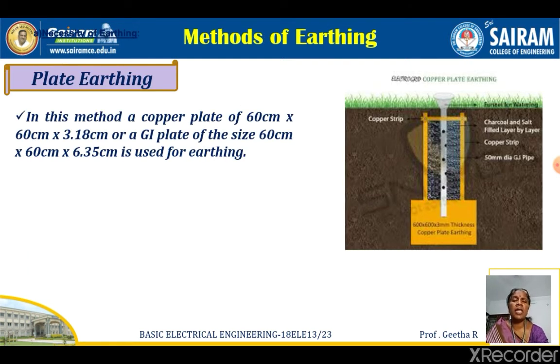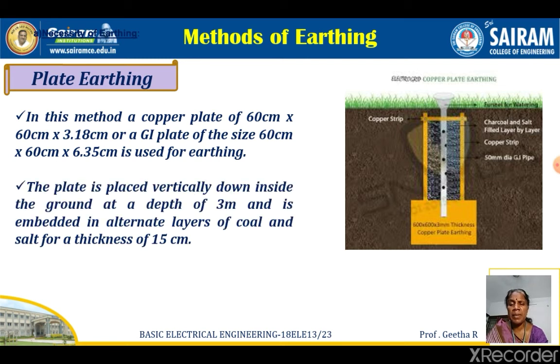Methods of earthing. There are two types of earthing called plate earthing and pipe earthing. Plate earthing is nothing but a copper plate that is kept inside the ground. In pipe earthing, a pipe is used for the earthing. In plate earthing, a copper plate of 60 centimeter by 60 centimeter by 3.18 centimeter, or a galvanized iron plate of the size 60 centimeter by 60 centimeter by 6.35 centimeter, is used for earthing. Since a copper plate is used, it is called plate earthing. The plate is placed vertically down inside the ground at a depth of 3 meters and is embedded in alternate layers of coal and salt for a thickness of 15 centimeter.